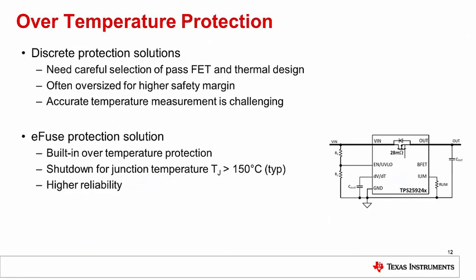Over temperature protection. Accurate temperature measurement in discrete solutions is challenging. So, discrete protection solutions need careful selection of FET and thermal design to keep the device within safe operating area limits under any extreme fault conditions. Whereas TI eFuses come with built-in over temperature protection and shut down if the junction temperature exceeds 150 degrees centigrade.